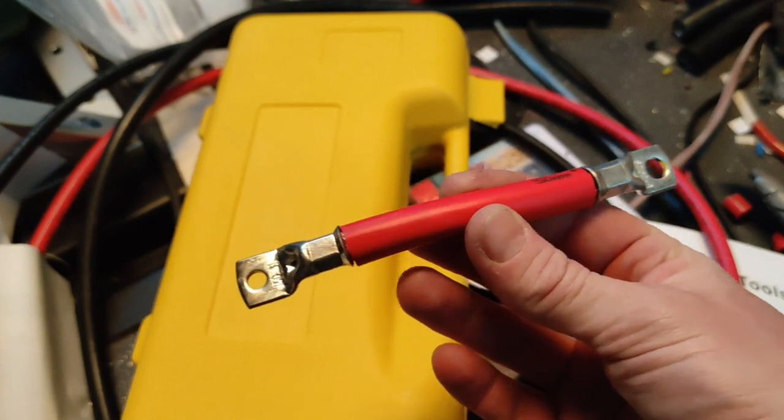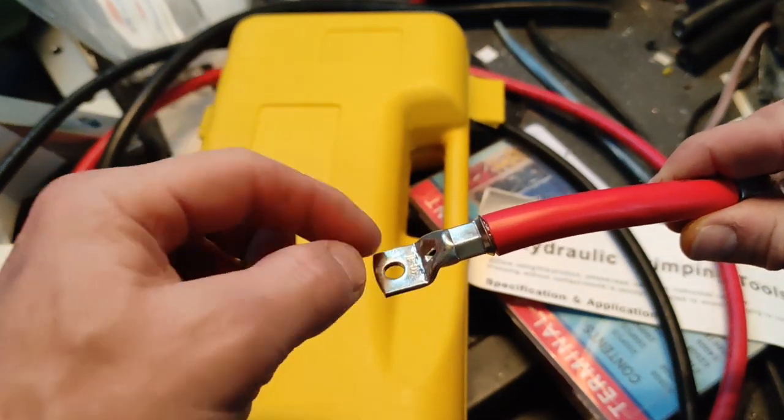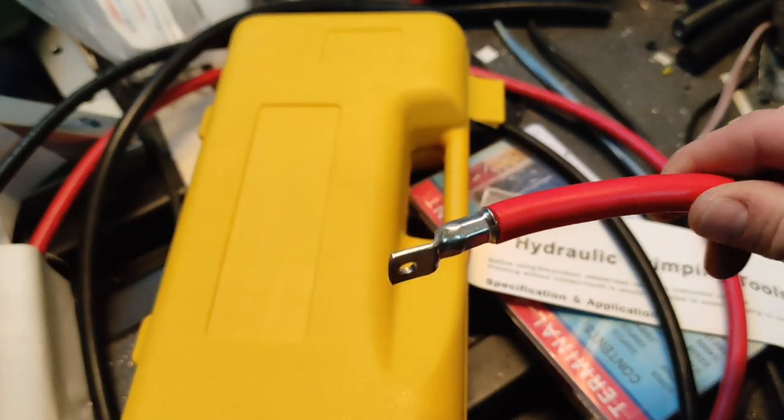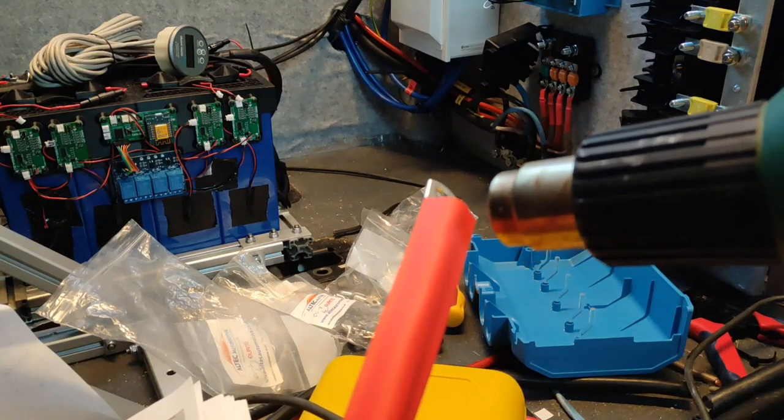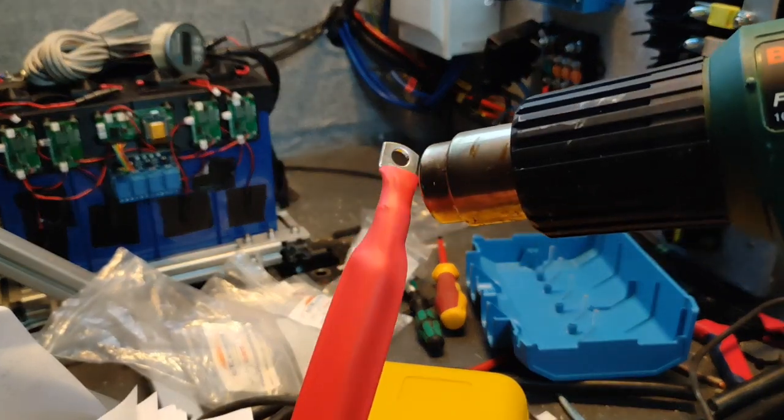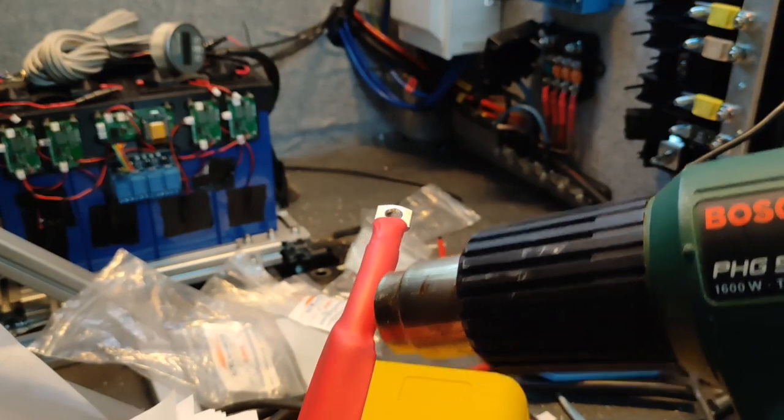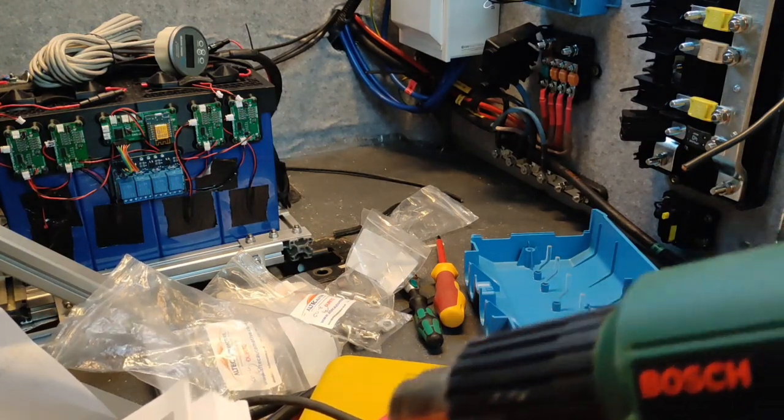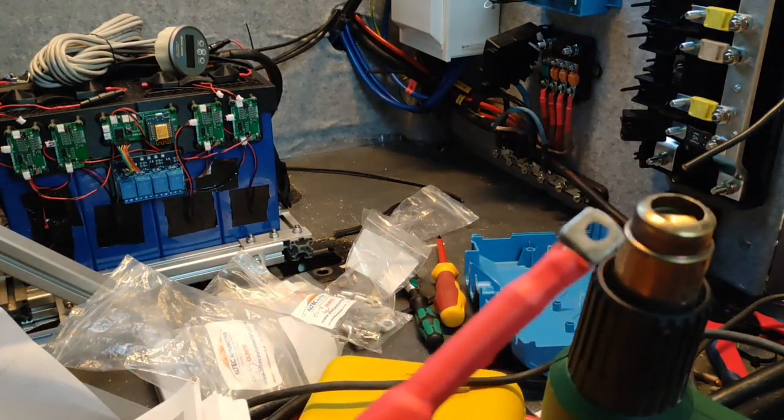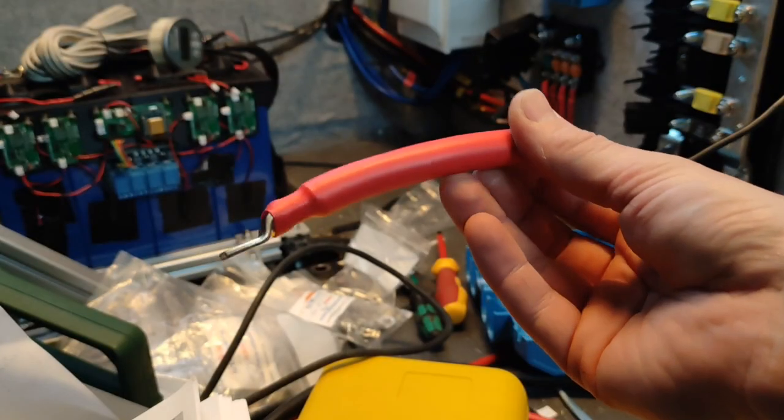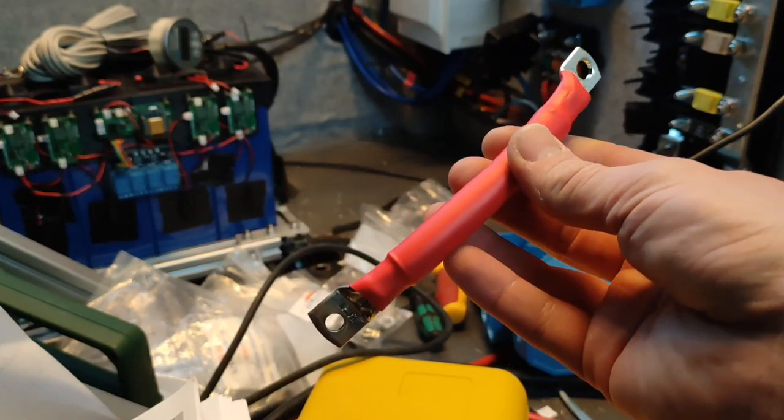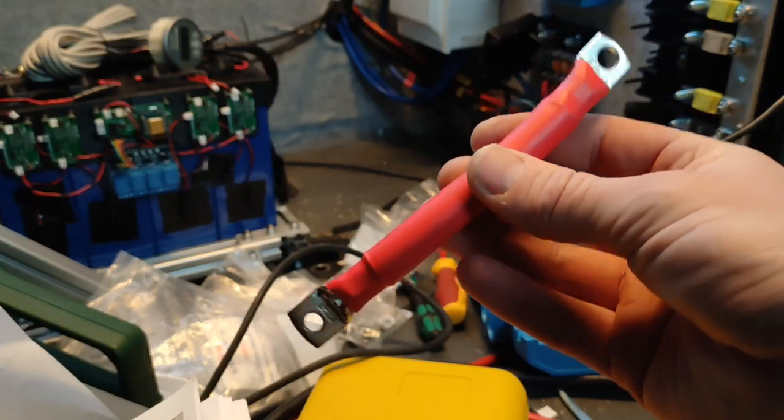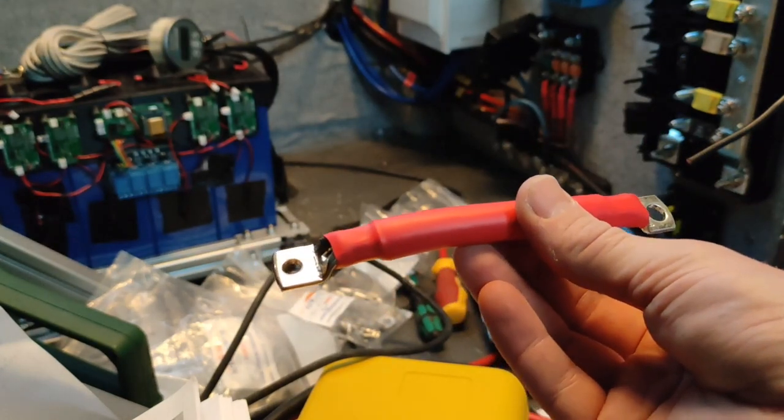So there we have the fully crimped cable, and now I'm going to put some heat shrink over the ends, again to cover up all of this exposed metal, so that only this section is left exposed so that it can be attached to the terminals. Now because I've got to do both ends and that's very hot, I've got to wait for this end to cool down before I can grab it to then do this end up. And here we have the finished cable. This is very similar to if you were making battery cables for paralleling cables. Nice short cable, good solid crimp connections, and then covering the ends, the exposed ends with heat shrink.